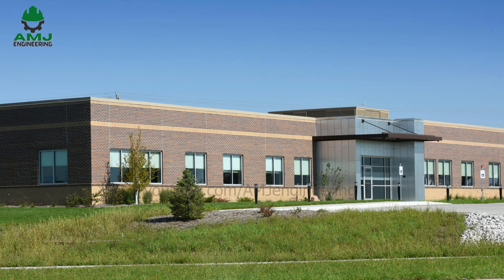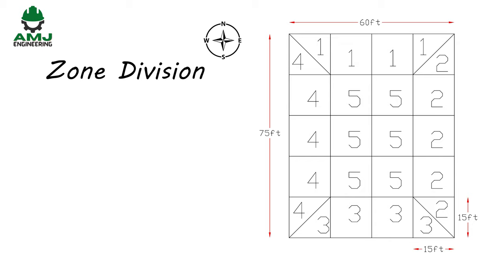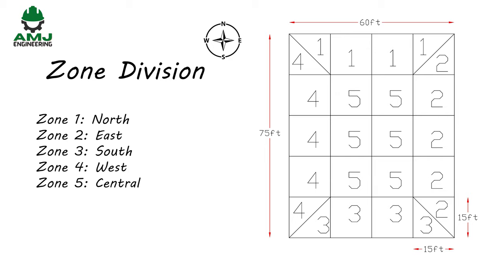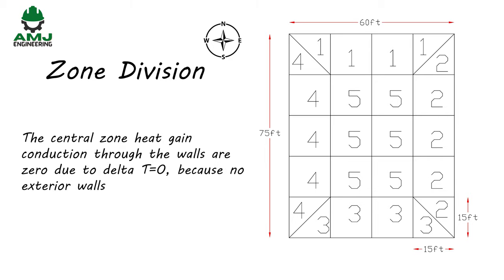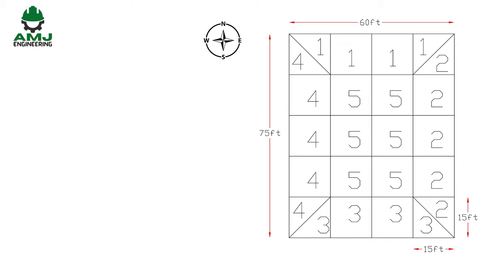The first step is to divide the area into zones. For simplicity, we assume the building consists of 20 offices of the same size. The building envelope is divided into 5 zones based on solar exposure of external walls. Zone 1 has north-facing walls, Zone 2 east-facing, Zones 3 and 4 south and west respectively. In Zone 5, the central zone, conduction heat gain through walls is zero because there are no exterior walls.